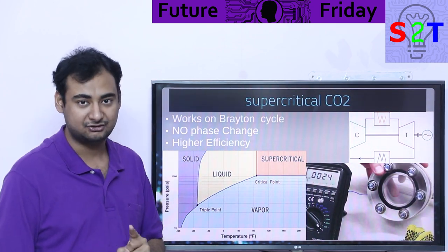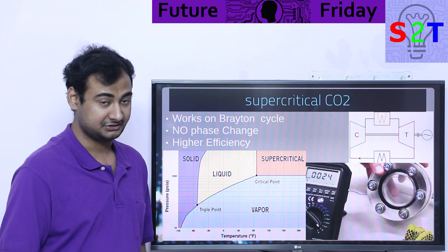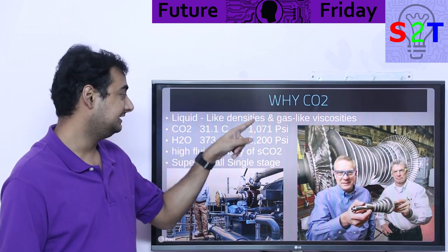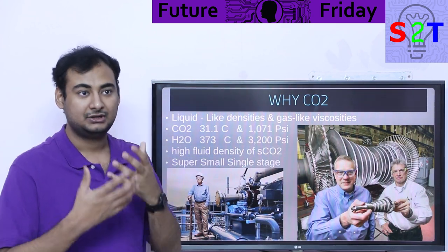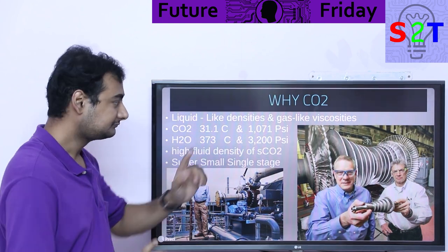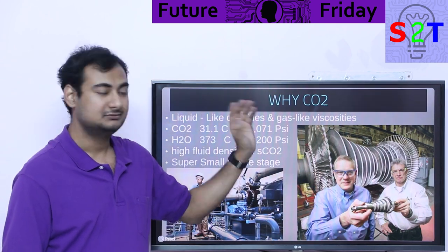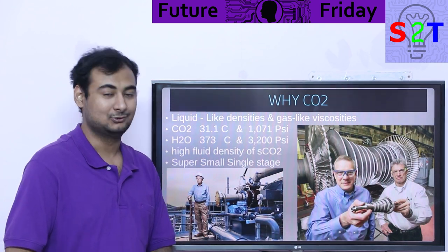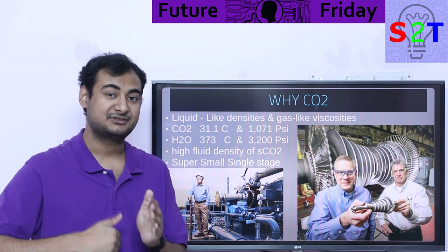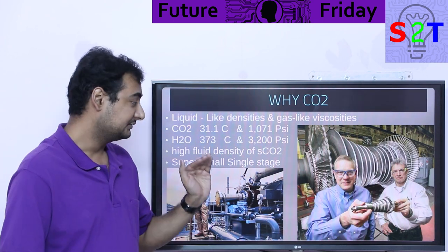The sole reason we deal with all this extra hassle is simply because it allows for higher efficiency — and significant enough that we're talking about something like 5% more efficient, which is a lot of money. Supercritical means liquid-like density and gas-like viscosity. If you're familiar with turbines, you know that denser the fluid, the more power you can extract in a smaller area. That big giant steam turbine versus this tiny one that a person can hold in their hands — that's a 10-megawatt carbon dioxide turbine. Its density is almost half that of water, so your turbine size is very small.